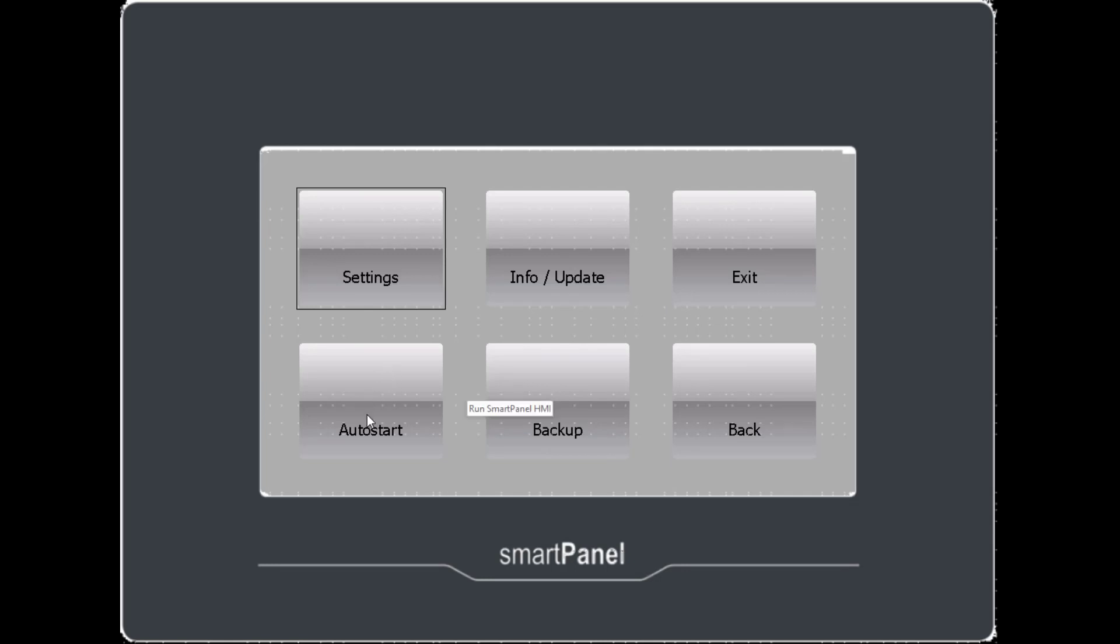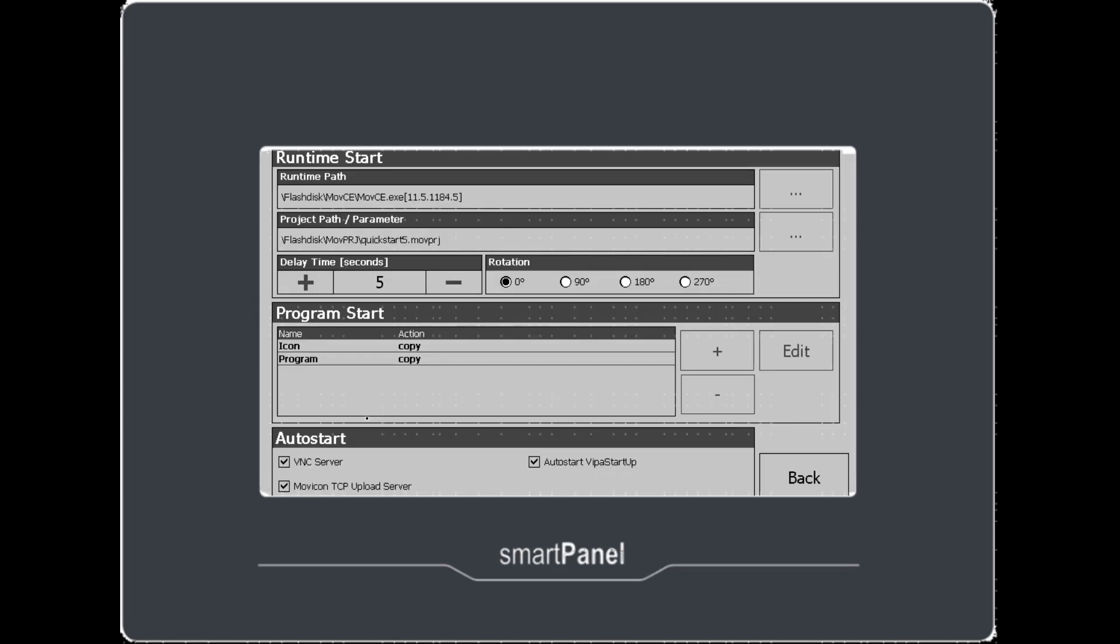Next look at Auto Start. There are a few settings under the Auto Start menu. And let's focus on the bottom first. You might as well check all of the boxes under Auto Start. VNC server allows you to use your computer to access the HMI. Like I'm doing right now to record this video using VNC viewer. Movicon TCP upload server must be selected so that you can upload the project from Movicon. Auto Start Vipa Startup causes the HMI project to load automatically.